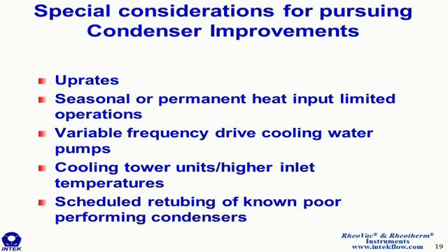If you have cooling tower units that result in high inlet temperatures, then any percent increase in heat transfer has a greater impact on the condenser pressure. So if the unit operates with high inlet temperatures, then there's additional economic incentive there.